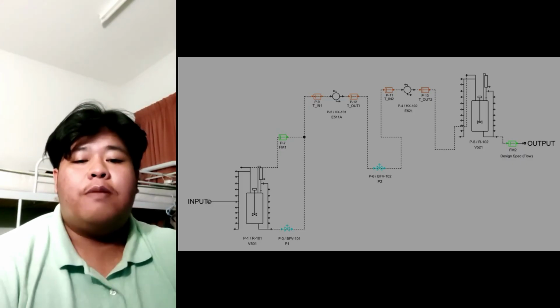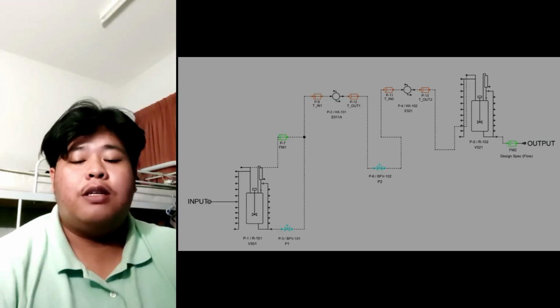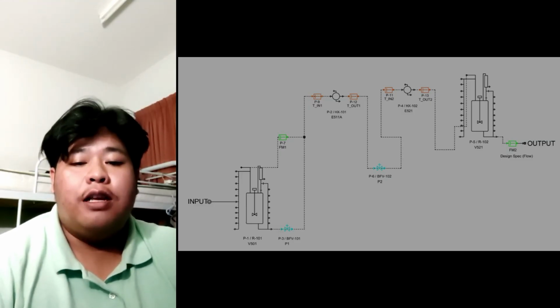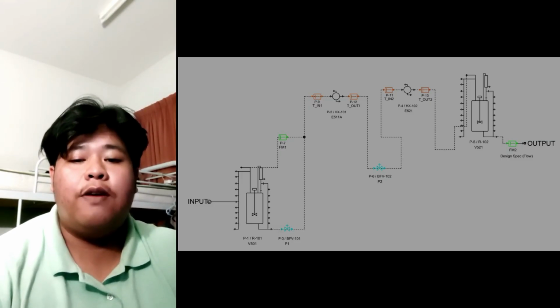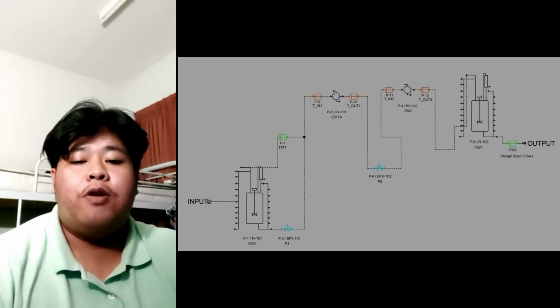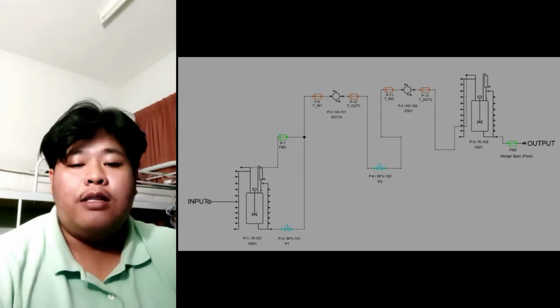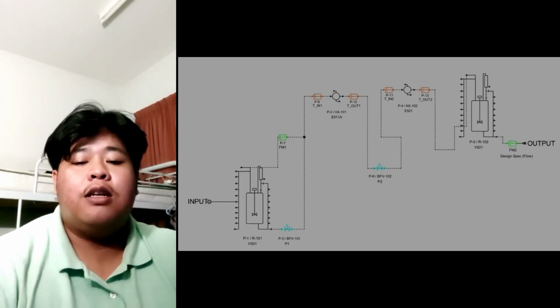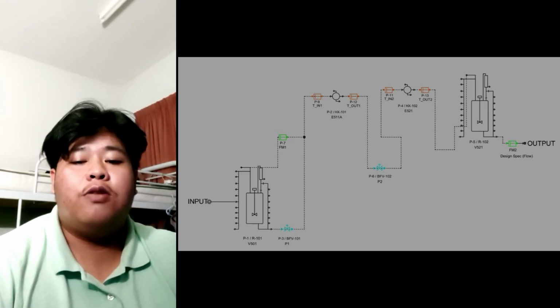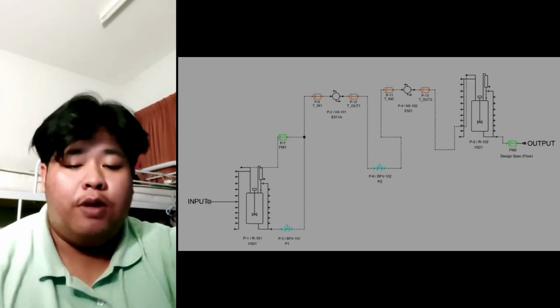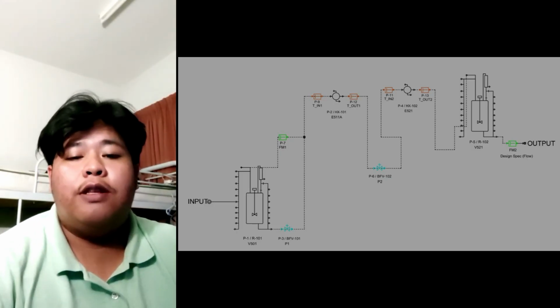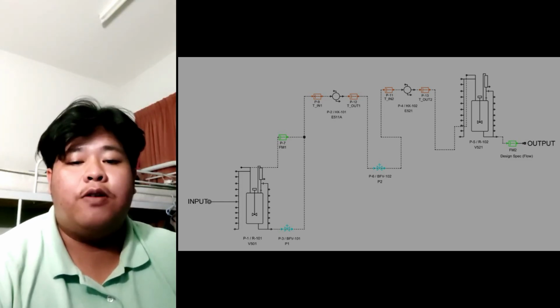We utilize the automatic butterfly valve, as mentioned in our report. Butterfly valves are ideal here because they handle large flow effectively. This will be driven by pneumatic actuators, chosen for their speed and reliability, allowing us to modulate flow instantly rather than relying on an operator to manually turn a wheel. The heart of this improvement is the PID feedback control system.